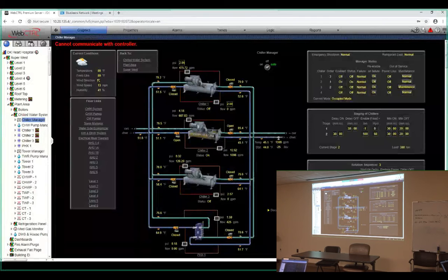I don't think you were here. Staging is based on load. So once we get over 500 tons, we'll stage up to the second chiller. When we drop back to 440 tons, then we'll stage back down to one chiller. And the system is lead lag with one redundant chiller.